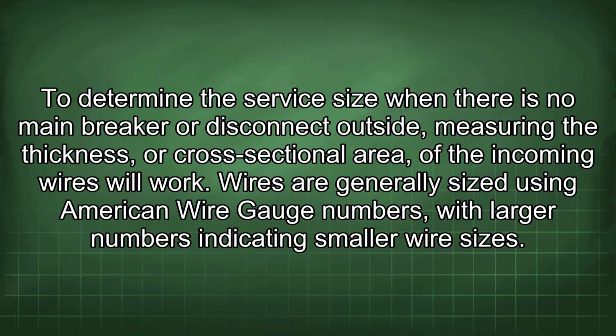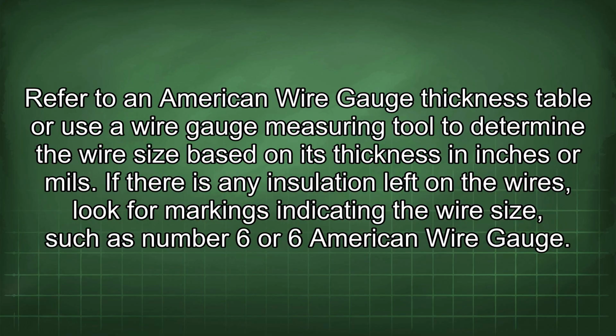To determine the service size when there is no main breaker or disconnect outside, measuring the thickness or cross-sectional area of the incoming wires will work. Wires are generally sized using American wire gauge numbers, with larger numbers indicating smaller wire sizes. Refer to an American wire gauge thickness table or use a wire gauge measuring tool to determine the wire size based on its thickness in inches or mils.